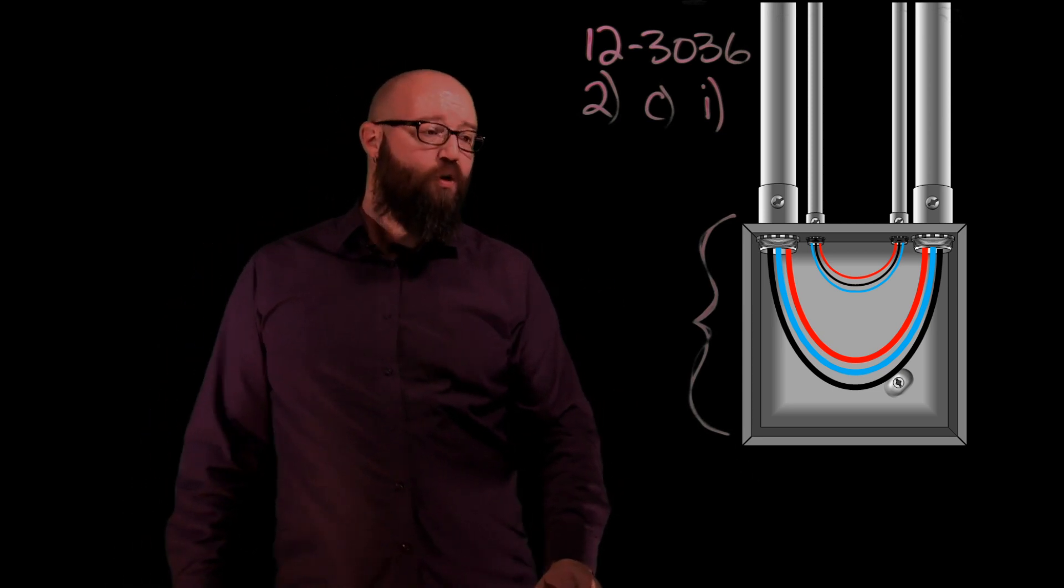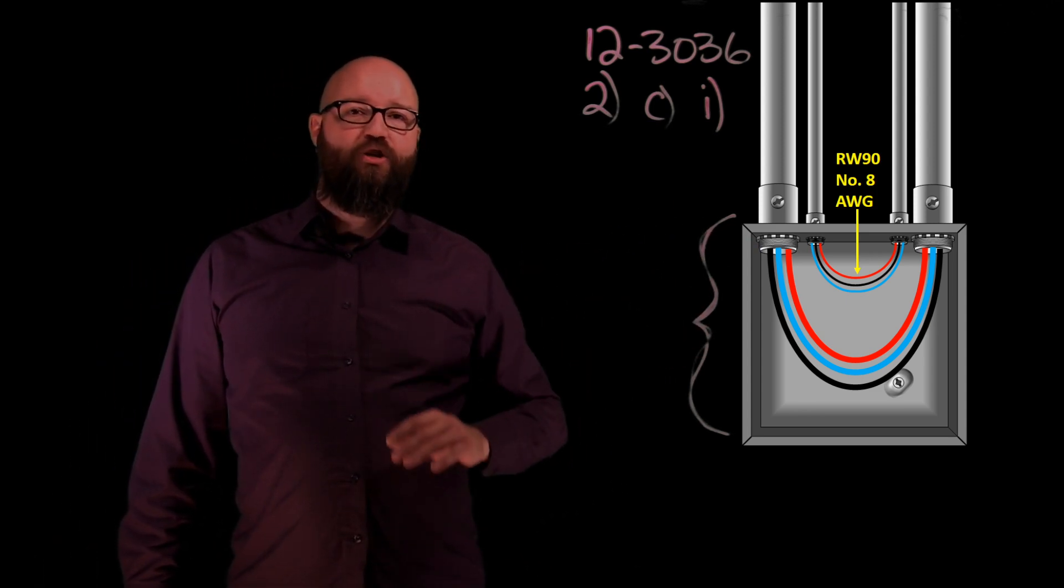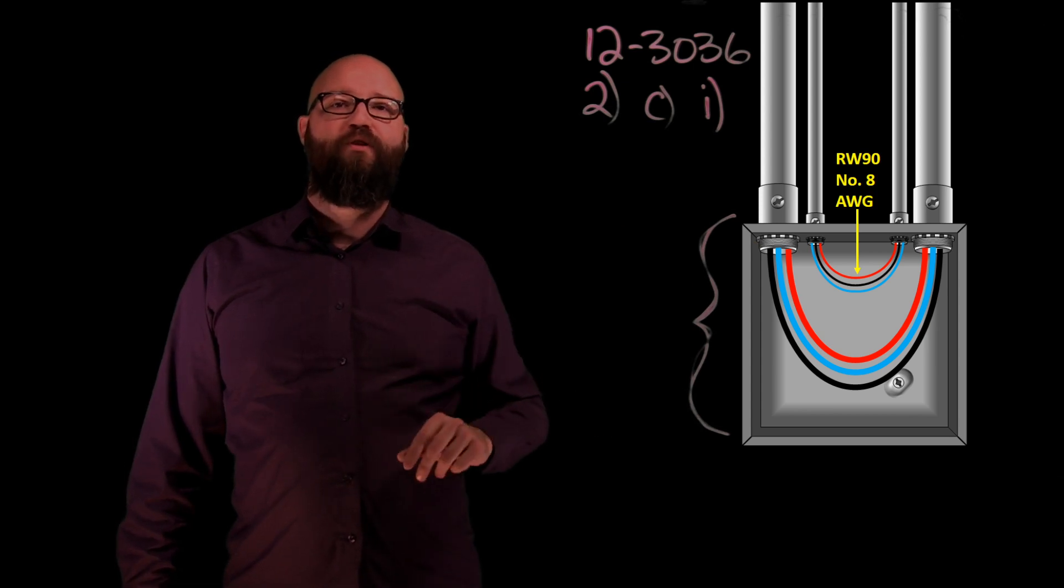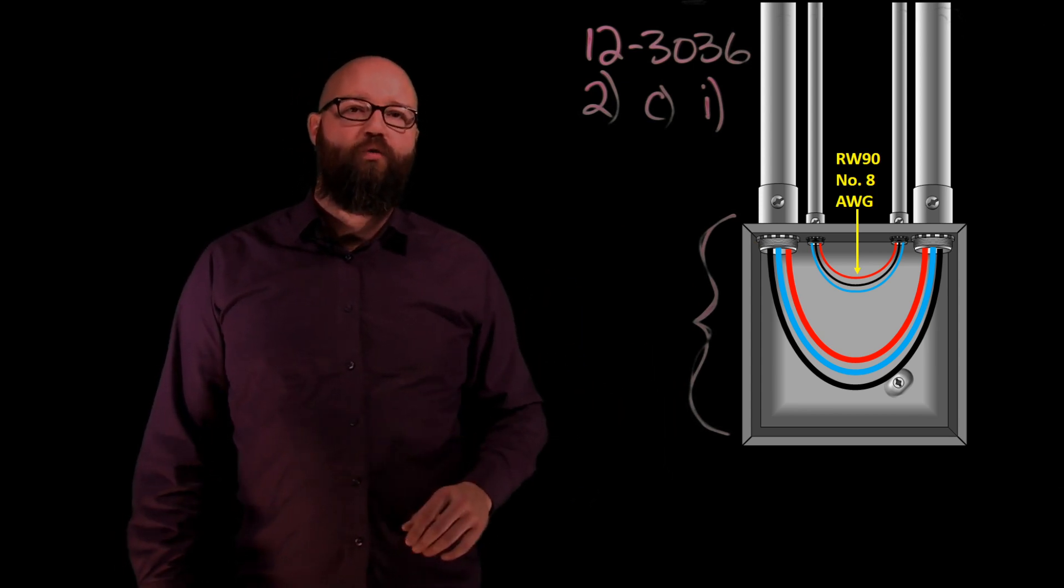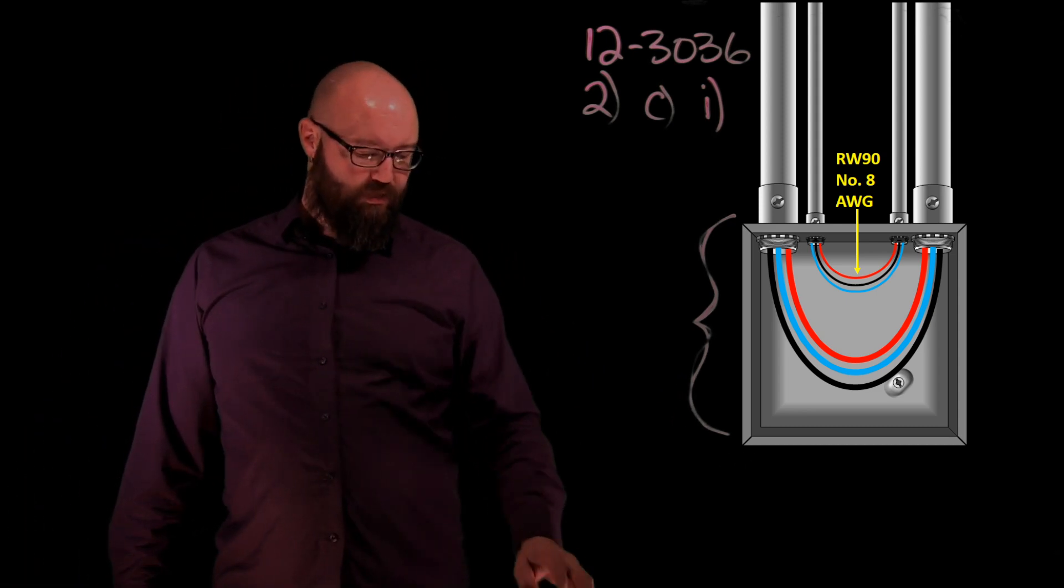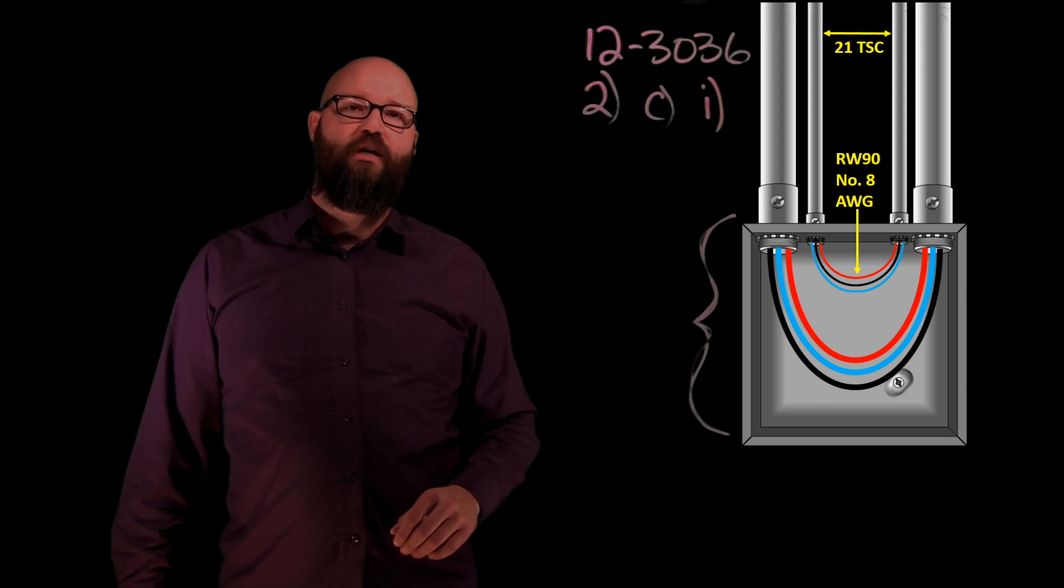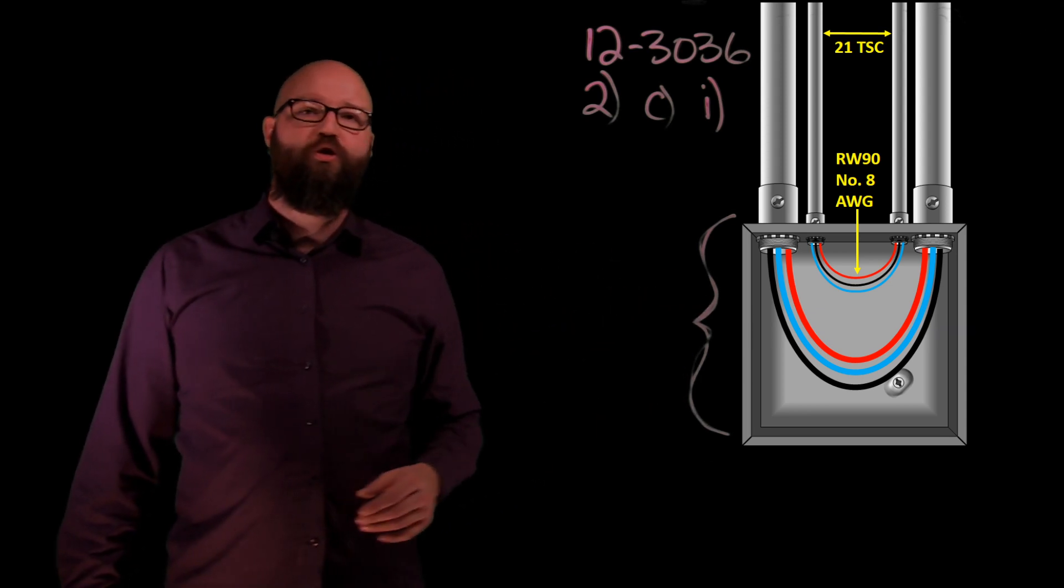I just want to point out our smaller conductors, those are going to be a number eight gauge. Those are dealt with in another rule 12-30-34 so we're not going to concern ourselves with those. But if we were to size the conduit for those, we would take those number eights with our RW90. Table six tells me that we would have a 21 trade size conduit to accommodate those number eights.